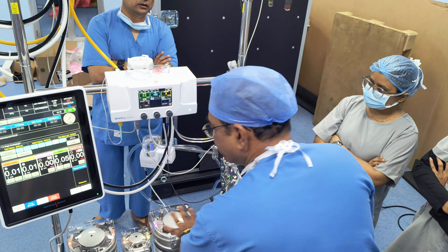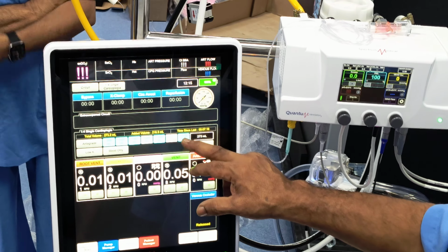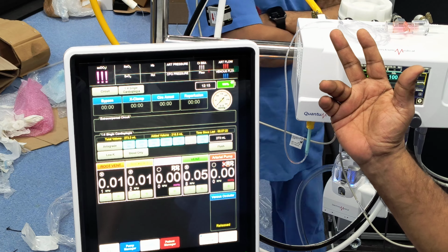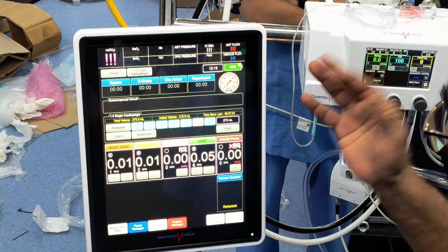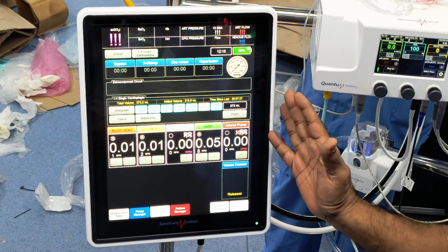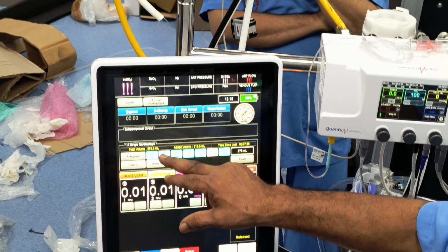Did you mention how the cardioplegia pump is interlinked with the arterial pump? Yeah, that was the minimum inlet pressure. Now tell the delivery feed. We have programmed certain volumes for you. For a 1 liter dose, you click on 1 liter, and if you want to increase it, you just press plus 100. During the run you can also increase or decrease. We have given 300, 500, 700. If you are doing pediatric, 500. After 500, if you still want to give more or less, the minute it touches here, it will stop.